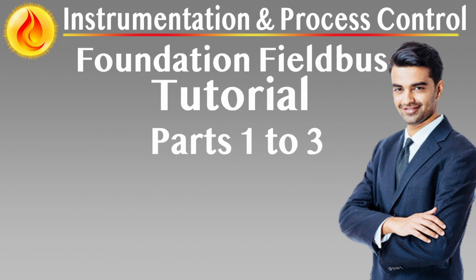protocol stack. Foundation Fieldbus systems integrate seamlessly with distributed control systems (DCS) through Fieldbus Interface Modules, FIMs, or Host Communication Modules, HCMs. These interface points enable centralized engineering, diagnostics, and alarm management while allowing control to remain decentralized in the field layer. Device configuration, calibration, and diagnostics are performed from the control room using integrated software tools.